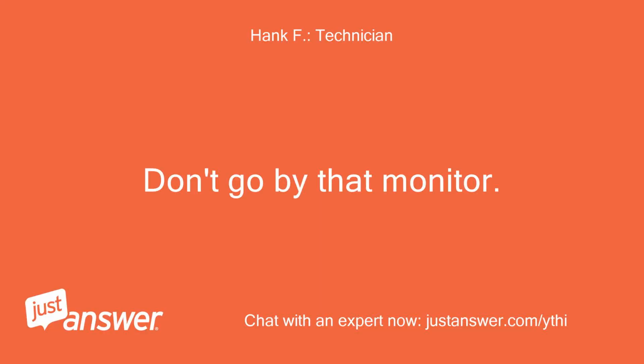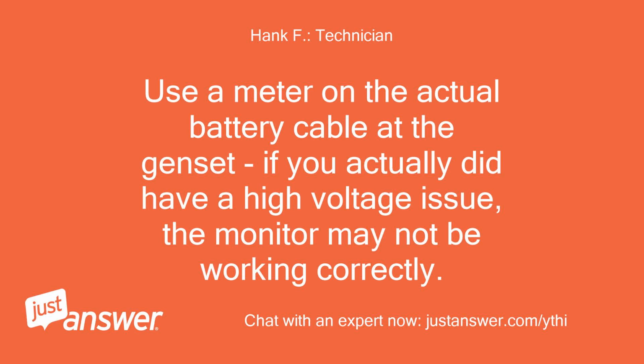Don't go by that monitor. Use a meter on the actual battery cable at the genset. If you actually did have a high voltage issue, the monitor may not be working correctly.